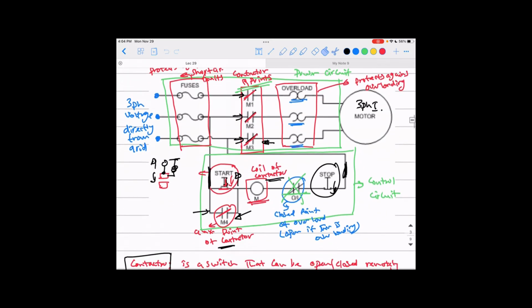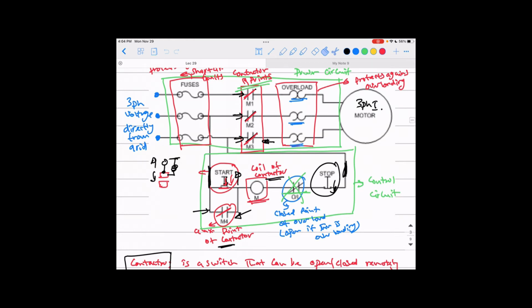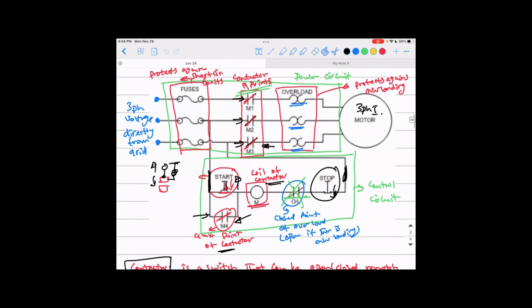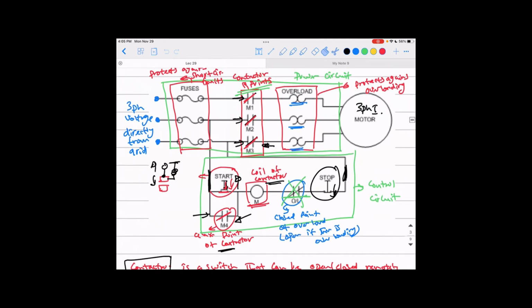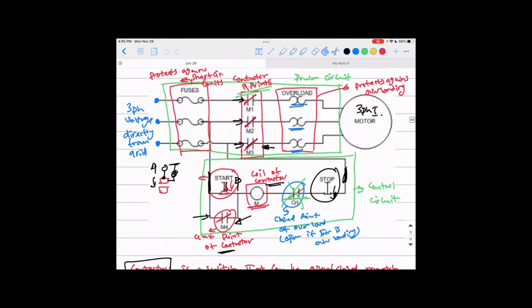And like we said last time, it's just how you can control the motor in terms of just starting and stopping. We don't control anything here, just a start and stop, and have a little bit of protection over the motor just to protect it. Obviously, if you're talking about a big motor that can be used for very big applications, you will need more protections, not just those simple protections with the fuse and overload. Sometimes you use a circuit breaker instead of the fuse, and you use different protection relays that can protect against undervoltage or overvoltage, earth leakage, all that stuff. But that's, like I said, for the protection courses, not here. So we're talking here about the standard protection you just find for a standard motor out there in a regular industrial application. Okay.